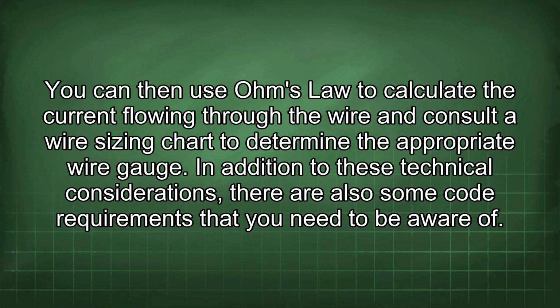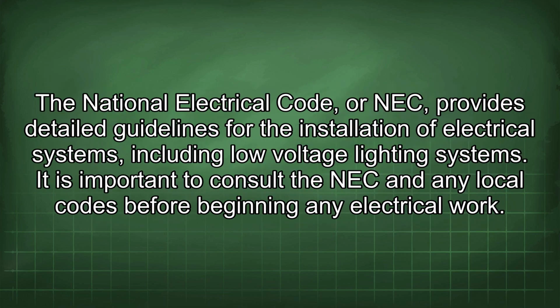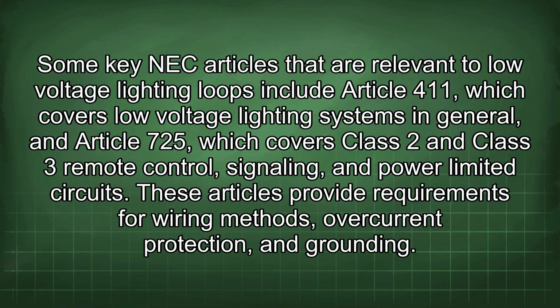In addition to these technical considerations, there are also some code requirements that you need to be aware of. The National Electrical Code, or NEC, provides detailed guidelines for the installation of electrical systems, including low-voltage lighting systems. It is important to consult the NEC and any local codes before beginning any electrical work. Some key NEC articles that are relevant to low-voltage lighting loops include Article 411, which covers low-voltage lighting systems in general, and Article 725, which covers Class 2 and Class 3 remote control, signaling, and power-limited circuits. These articles provide requirements for wiring methods, overcurrent protection, and grounding.